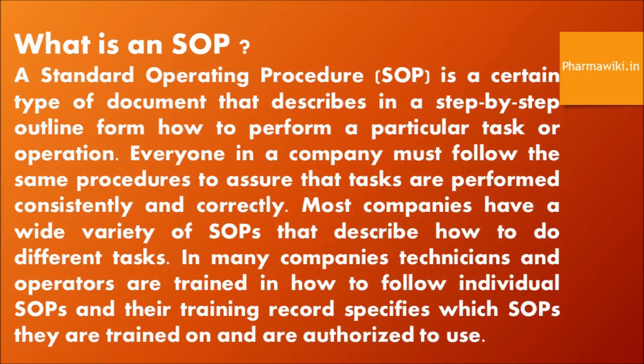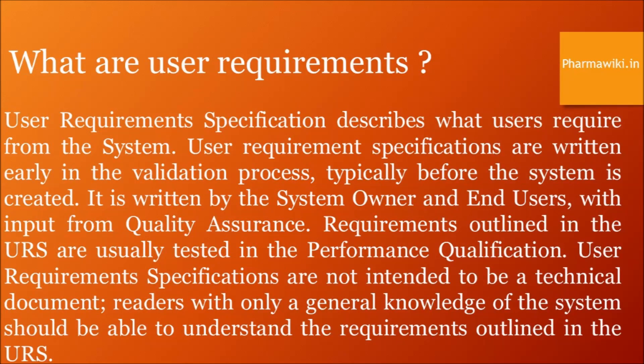What are user requirements? User requirements specifications are written early in the validation process, typically before the system is created. They are written by the system owner and end users, with input from quality assurance. Requirements outlined in the URS are usually tested in the performance qualification. User requirements specifications are not intended to be a technical document — readers with only a general knowledge of the system should be able to understand the requirements outlined in the URS.